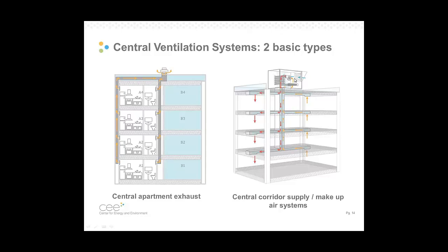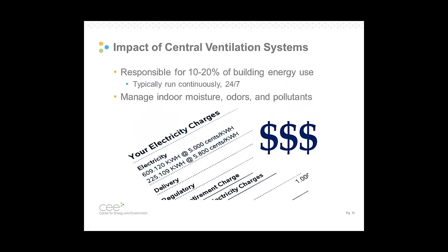There may or may not be return air, as in this diagram, so sometimes it's just 100% supply air delivered via supply ducts only. This one has return air, where the recirculated air mixes with the outdoor air here in the air handler. Two ways to do it.